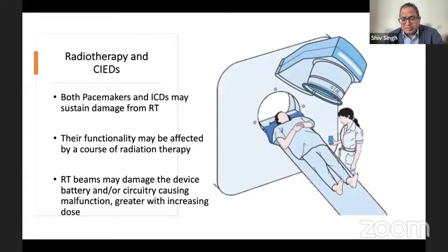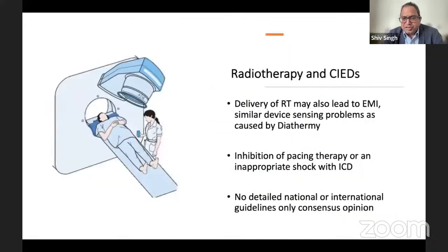Radiotherapy and pacemakers and other things. This is very important because here, both pacemakers and ICDs can sustain injuries. I mean, the units from the radiotherapy are using very high energy gamma rays or other rays, and the function can be affected by radiation therapy. The radiotherapy beams can damage the batteries or the circuit and cause malfunction. So in these cases, you need to make sure that the pacemakers are put into an asynchronous mode, and you need to interrogate the unit after the procedure. Unfortunately, there are no detailed national or international guidelines or consensus about radiotherapy. So these are special kinds of patients where we need to be careful with the use of diathermy.